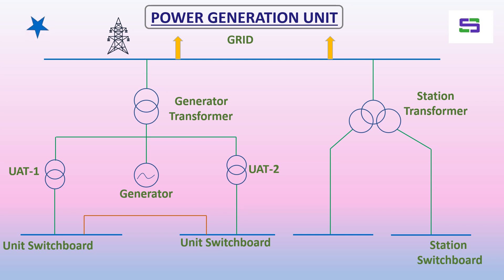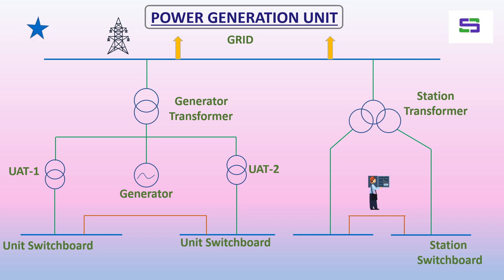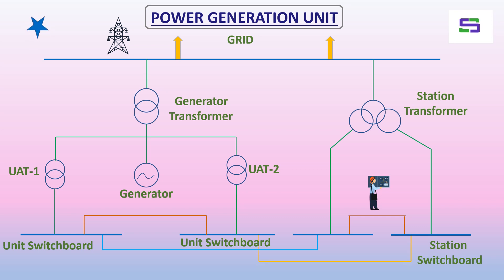The station switchboards feed supply to the common auxiliary systems in the power plant. There is a bus coupler between these two switchboards, and there will also be bus changeover — automatic bus transfer — so the FBT or ABT panel will be there. Between the unit switchboard and station switchboards there is coupling, and normally those breakers are kept open.